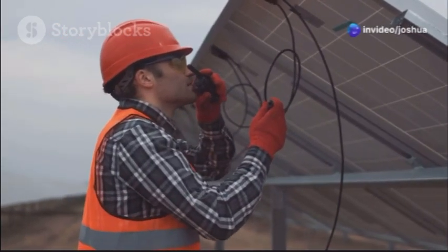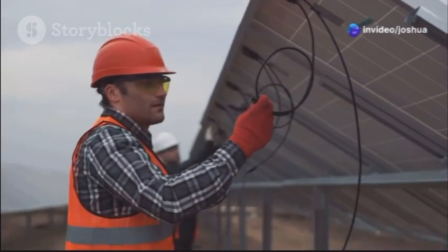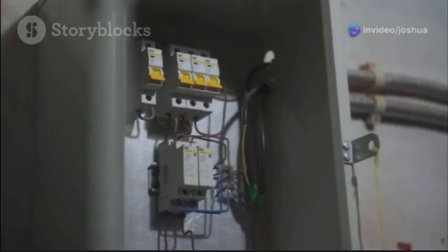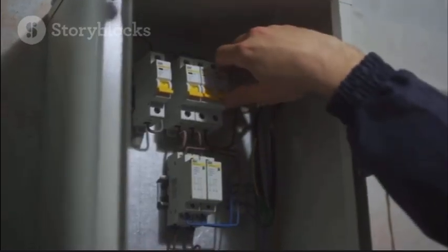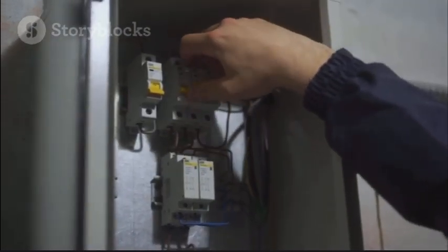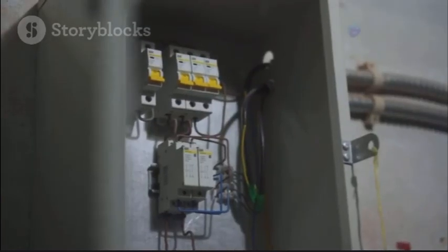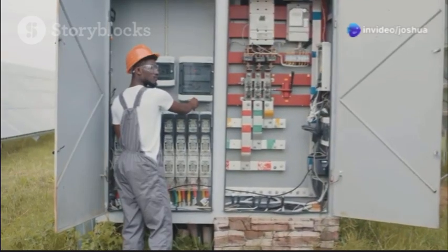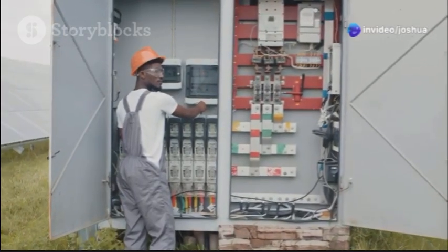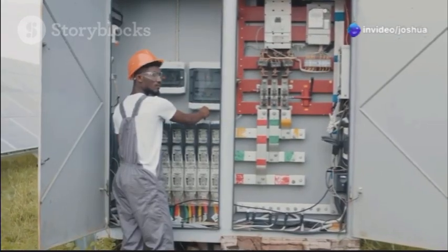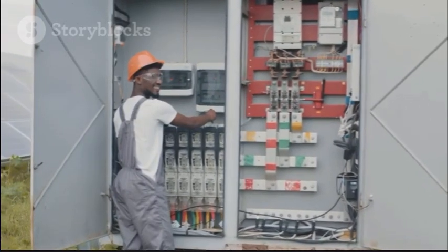Step 4, grid connection. Safety and code compliance are key here. Connect the inverter's AC output terminals to your main electrical panel through a dedicated circuit breaker. This ensures your system can be safely isolated if needed. This step may require a qualified electrician, so don't hesitate to call in a pro if needed. Local regulations may require professional sign-off.